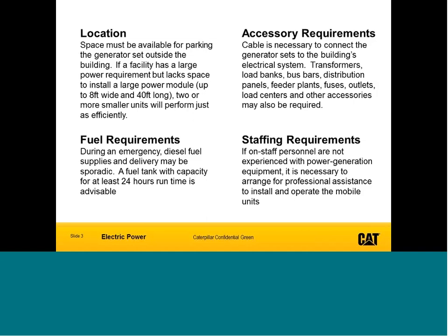The next thing you want to do is walk around your facility and look at where you would put a temporary generator if called upon. Look for areas that are easily accessible from the road and in relative proximity to your power generation main circuit breaker. You'll also want to make sure this area has relatively stable footing and isn't in a spot where water would naturally flow in a flood event. You also want to do a quick scan to see if there are any trees or other hazards that could become a hindrance to reaching that location in the event of an outage.